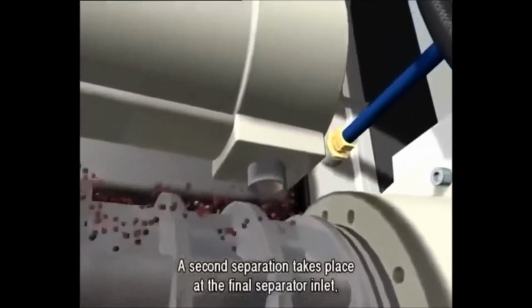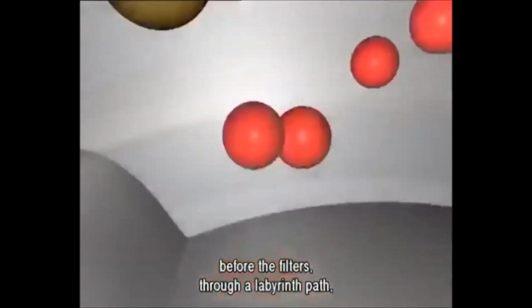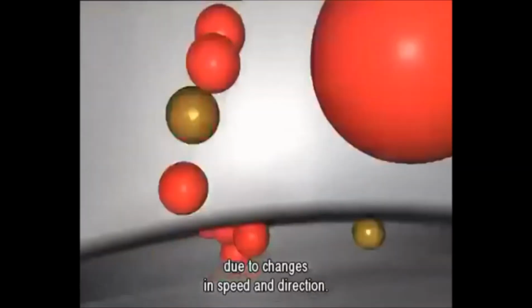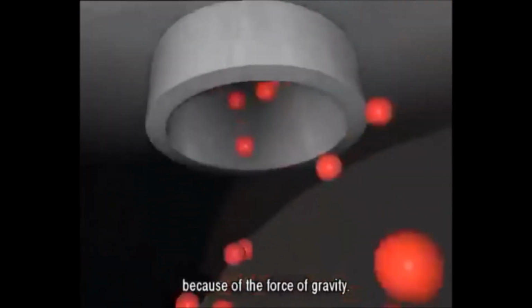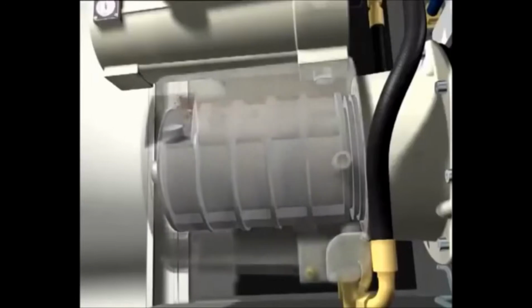A second separation takes place at the final separator inlet before the filters through a labyrinth path due to changes in speed and direction. During this phase, the oil particles tend to drop down because of the force of gravity.